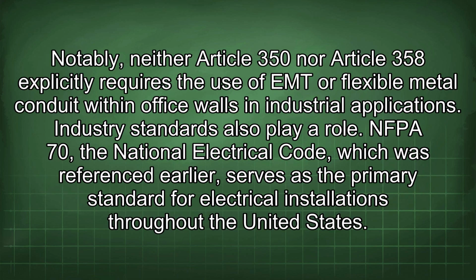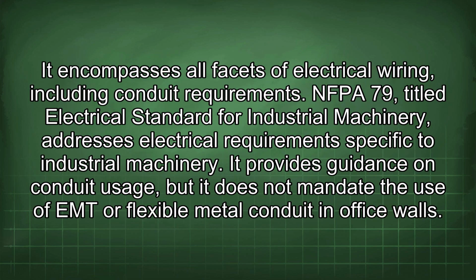Notably, neither Article 350 nor Article 358 explicitly requires the use of EMT or flexible metal conduit within office walls in industrial applications. Industry standards also play a role. NFPA 70, the National Electrical Code, which was referenced earlier, serves as the primary standard for electrical installations throughout the United States. It encompasses all facets of electrical wiring, including conduit requirements. NFPA 79, titled Electrical Standard for Industrial Machinery, addresses electrical requirements specific to industrial machinery.